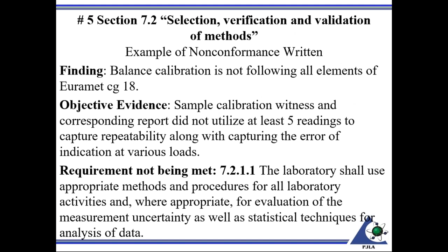So here's an example of a non-conformance written. Like I said, it has to be appropriate procedures. And if the procedure is being followed, it needs to be followed as it's written. If it deviates from it, then you're not following it. And that's an example of this particular non-conformance, where the finding was a balanced calibration is not following all elements of the Euramet cg 18 procedure.